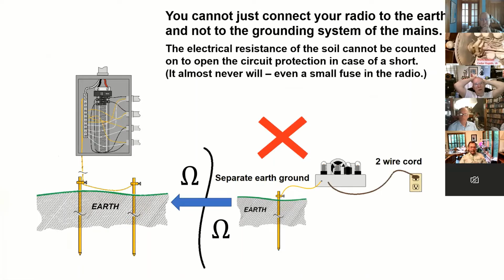You cannot just connect your radio to earth. Some people do this with antennas, but that's different. There's not enough current going to flow through the earth to substitute for that ground wire going all the way back to the panel and connecting to the neutral bus. There might be 1,000 ohms or 10,000 ohms between that neutral bus and the earth, depending on how wet it is, etc. Again, we're trying to throw the ground in and say that, oh, my radio is grounded, when you've got a 2-wire cord. Does that make sense, everyone? I hope. Yes.